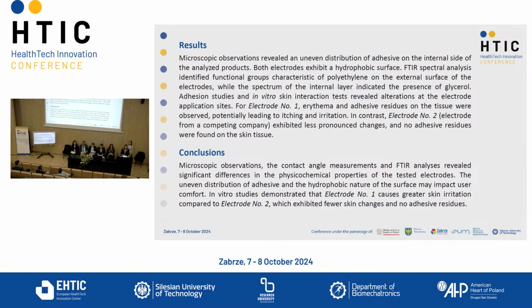The uneven distribution of adhesive and hydrophobic nature of the surface may impact the patient's comfort. In vitro studies demonstrated that electrode number 1 causes greater skin irritations and shows cytotoxic effects in the mentioned dilutions compared to electrode number 2, which exhibited fewer skin changes and no adhesive residues.